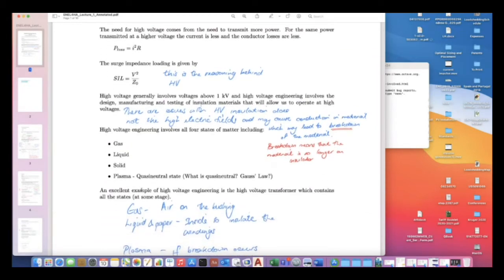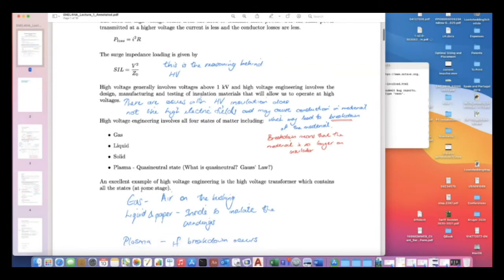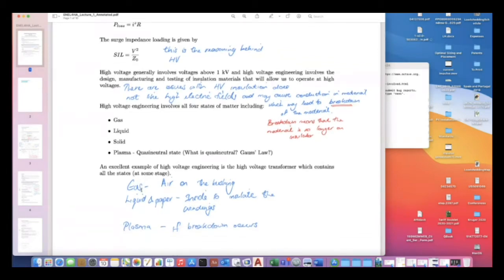So high voltage, again, involves voltages above 1 kV. And high voltage engineering involves the design, manufacture, and testing of insulation materials that allow us to operate at high voltages. If we're operating at high voltages, we know that there are going to be high electric fields. The high electric fields cause different mechanisms in insulation material than just insulating. So this may lead to breakdown of the material. Breakdown basically means that it is no longer an insulator.